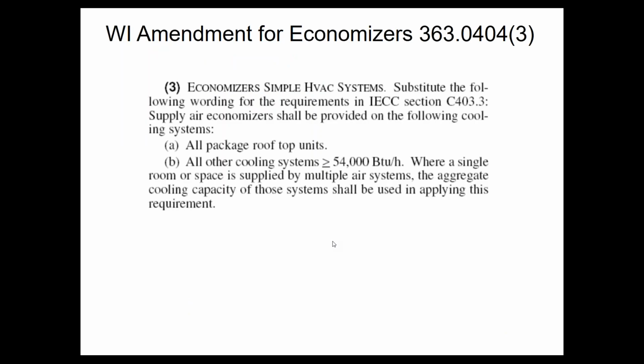In Wisconsin, there's an amendment to that. It's still the 54,000 BTUs for most systems. However, for packaged rooftops, it's all packaged rooftops. So that would also include 4-ton, 3-ton, 2-ton type units that you have to do the economizer for in Wisconsin per the amendment.